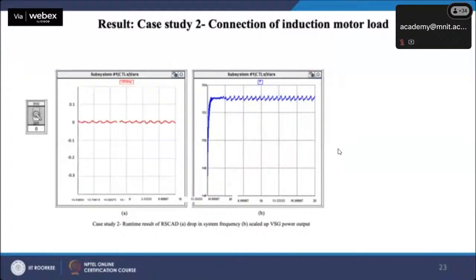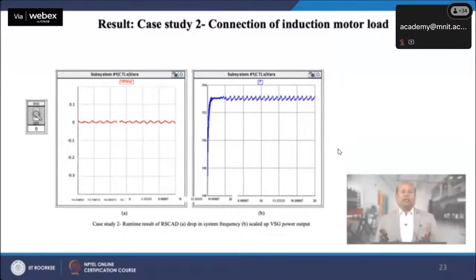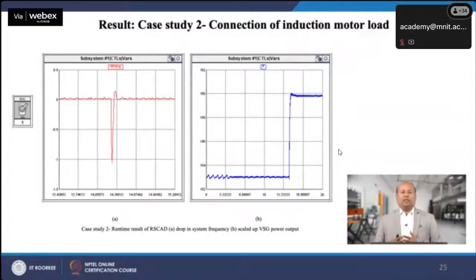The second case study corresponds to connection of an induction motor. Similar to case study 1, switch SW2 is utilized to connect the induction motor load. Initially the system is stable, as it can be observed from the frequency profile in runtime.